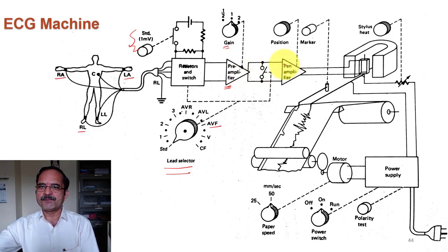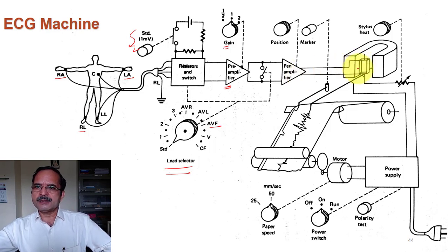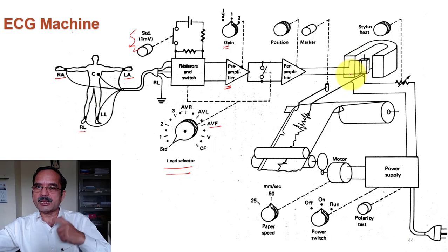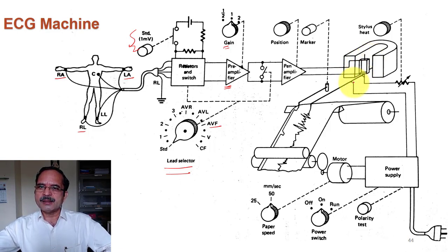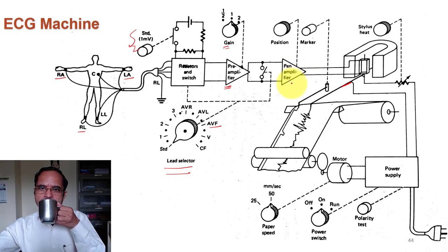The output of the pen amplifier is given to the plotter — that is why it is called the pen amplifier. This is a mechanical plotter — a galvanometer type of arrangement. There is a permanent magnet, there is a coil, and there is a pen. The motion of this pen is controlled by the electrical signal available at the output of the pen amplifier.